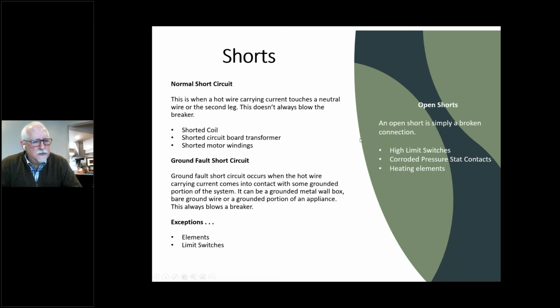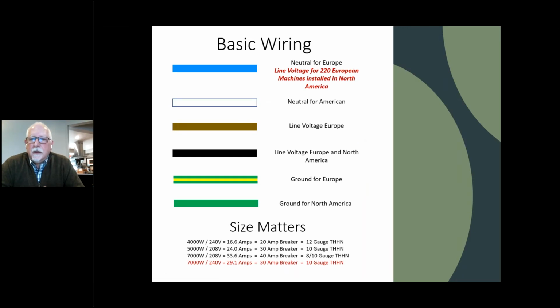So next, because we're getting close to 30. Okay, basic wiring. I tried to cover different colors for different applications, because this is what you're going to see typically on the cord of the machine. For European machines, blue is always neutral. And it's neutral almost everywhere else in the world where what you have coming out of the wall is 240 for everything. In the US, that blue wire actually carries current because we use that blue wire as the other leg to achieve 208 or 240 volts to the machine. So this is the one distinction where one wire carries two loads.